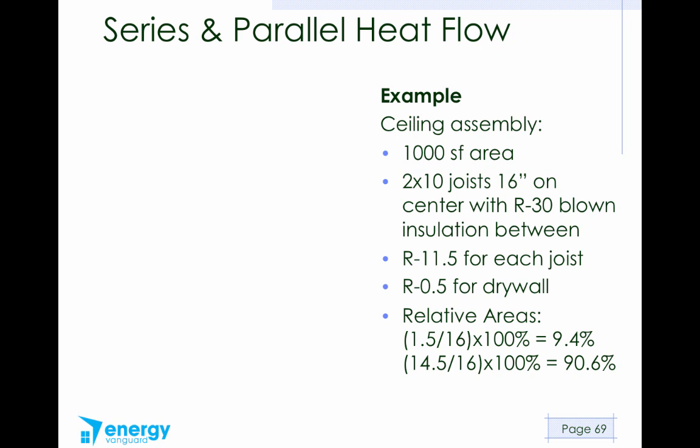The next thing we need to know is the area. So the joists are 1.5 inches wide. A 2 by 10 is 1½ by 9¼. So the width is 1½. We've got 16 inches on center, so the cavity is 14½ inches. And the relative areas then would be 1.5 divided by 16. So out of every 16 inches across, we're going to have 1½ inches of the ceiling joist. If we do that division, multiply by 100%, that's 9.4% of the area will be ceiling joist. And 14½ out of 16 is 90.6% of all the area will be the insulation.